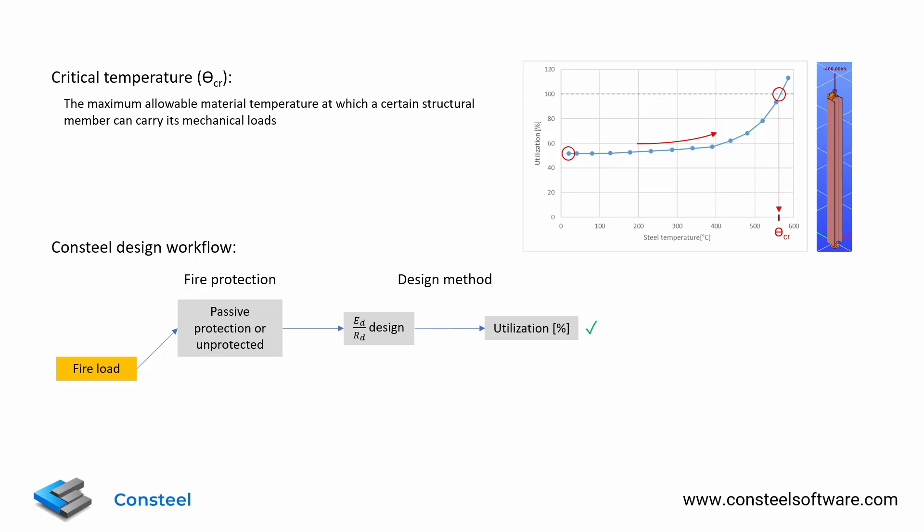If there is any fire protection on the member, we need to know its heat insulation capability to get this elevated temperature in a certain fire situation. In case of passive protections like gypsum boards or sprayed cement, we know this insulation value so we can use this assessment method.